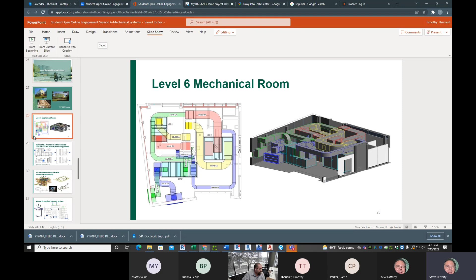The wheel spins up to the upper portion, or lower portion in our case, and new outside air that comes in that's hot gets to effectively reuse that cooling and the enthalpy out of the air to cool down the air before it even makes it to the air handler. So that's what our system is doing. It takes the return air, exhaust air mix and blows through the unit through a fan to the outside. It brings in the outside air through here, hits the cooler part that's already been pre-cooled by this other air that went through as the wheel spins.